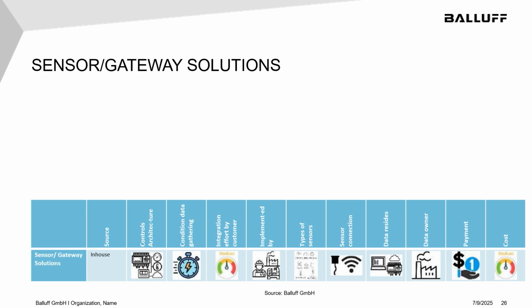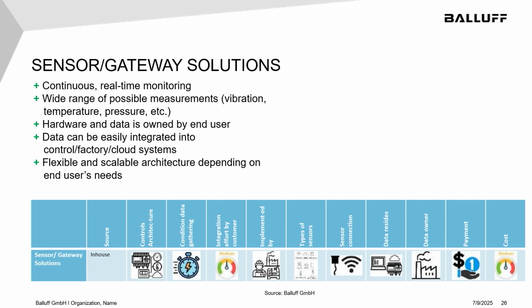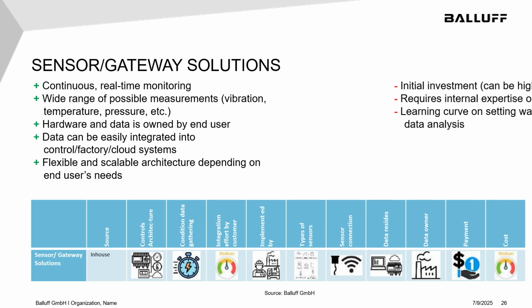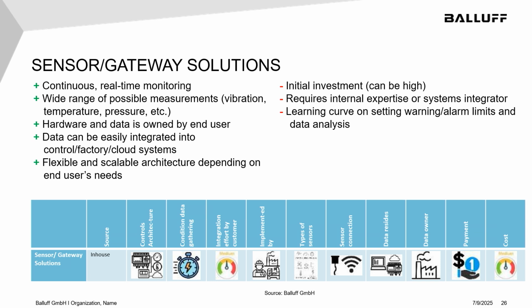And then finally, sensor and gateway solutions. They're really good at continuous real-time monitoring and can be tied directly into your control system like any other sensor. There's a wide range of measurements possible, whatever sensor you want to apply, whether it's a vibration sensor, pressure or flow. The data can be easily integrated into your system. You own that data. On the other hand, the initial investment up front is relatively high. Generally, either you or a systems integrator are going to have to install that system.